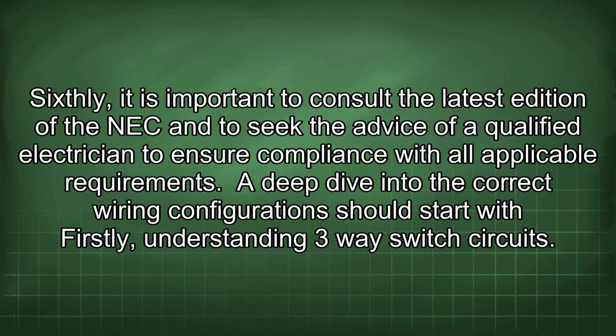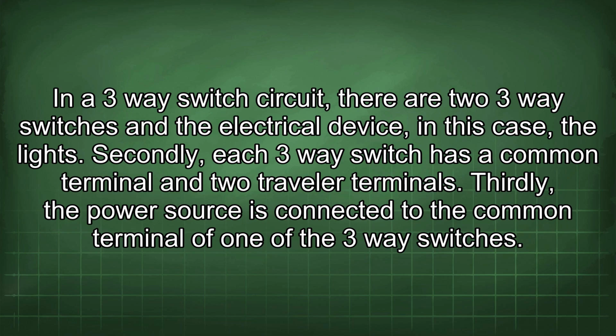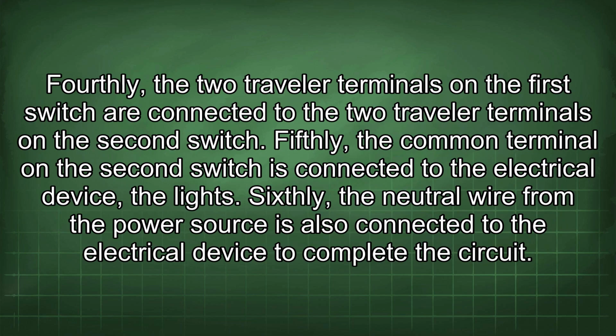A deep dive into the correct wiring configurations should start with, firstly, understanding three-way switch circuits. In a three-way switch circuit, there are two three-way switches and the electrical device, in this case, the lights. Secondly, each three-way switch has a common terminal and two traveler terminals. Thirdly, the power source is connected to the common terminal of one of the three-way switches. Fourthly, the two traveler terminals on the first switch are connected to the two traveler terminals on the second switch.